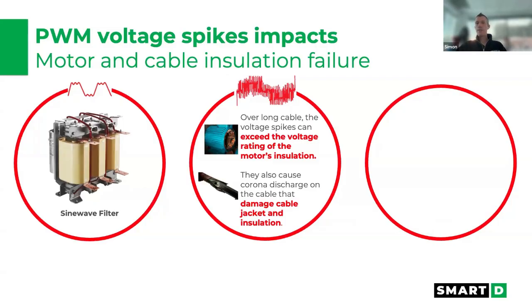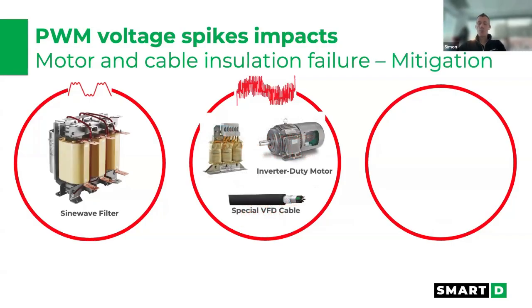And so that not only potentially damages the cable, but also the motor insulation. And so typically, this is why we're going to mandate inverter duty motors. We're going to mandate higher voltage rated cables, and depending on the length, we're going to require a choke, a dV/dt filter, or a sine wave filter.